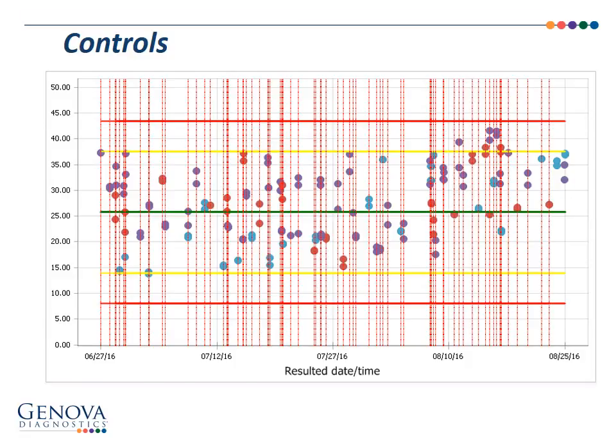You can also get situations like this, where the CVs are running just fine, and then something shifts. In this situation, we had a calibrator change, and it changed the values of our patients. And this is most evident quickly in the controls. So in this case, we need to go back and take a look at that change and make sure that it was appropriate.